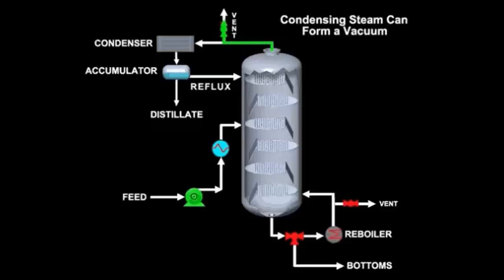Open the vent to the column as a safeguard. Add enough water to the column to fill the bottom sump. Next, start the reboiler to create steam from the water in the sump.